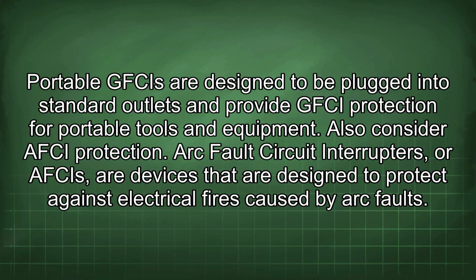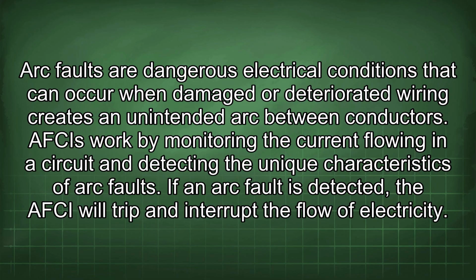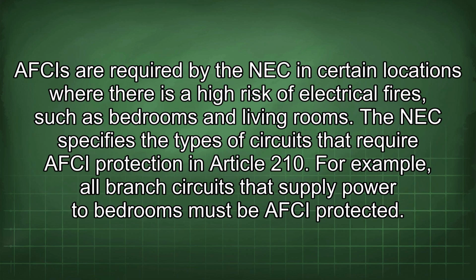Also consider AFCI protection. Arc fault circuit interrupters, or AFCIs, are devices that are designed to protect against electrical fires caused by arc faults. Arc faults are dangerous electrical conditions that can occur when damaged or deteriorated wiring creates an unintended arc between conductors. AFCIs work by monitoring the current flowing in a circuit and detecting the unique characteristics of arc faults. If an arc fault is detected, the AFCI will trip and interrupt the flow of electricity. AFCIs are required by the NEC in certain locations where there is a high risk of electrical fires, such as bedrooms and living rooms. The NEC specifies the types of circuits that require AFCI protection in Article 210.